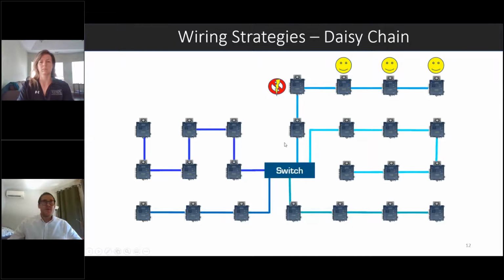And another thing to think about with your daisy chain strategy, always keep in mind, I labeled it as the rule of 50. So for IP communication, Cat6, Cat5 cabling, your Ethernet maximum distance is 100 meters. So you really don't want to have more than 50 meters between any individual controller. The reason being, say you had a situation such as this and you lost power here, as long as this whole link doesn't exceed 100 meters, you're still good with that communication. It's not exceeding your Ethernet maximum length there.